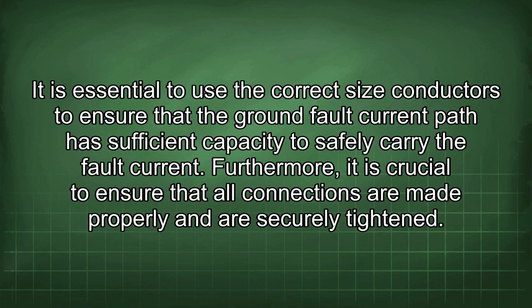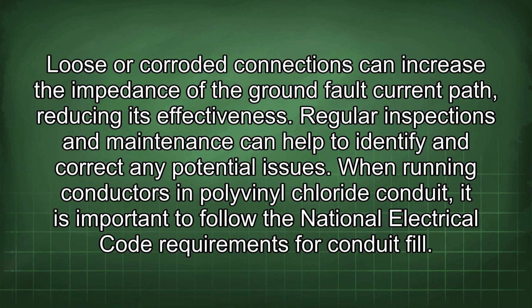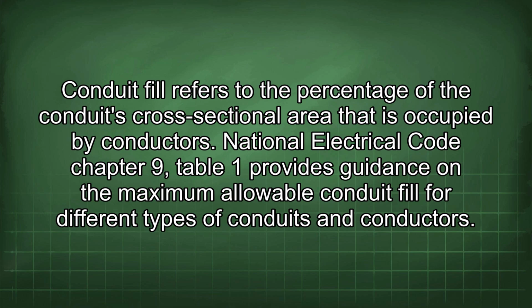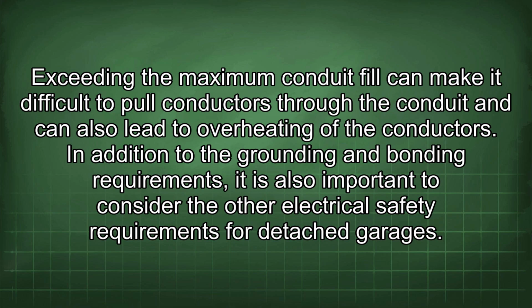Furthermore, it is crucial to ensure that all connections are made properly and are securely tightened. Loose or corroded connections can increase the impedance of the ground fault current path, reducing its effectiveness. Regular inspections and maintenance can help to identify and correct any potential issues. When running conductors in polyvinyl chloride conduit, it is important to follow the National Electrical Code requirements for conduit fill. Conduit fill refers to the percentage of the conduit's cross-sectional area that is occupied by conductors. National Electrical Code Chapter 9, Table 1 provides guidance on the maximum allowable conduit fill for different types of conduits and conductors. Exceeding the maximum conduit fill can make it difficult to pull conductors through the conduit and can also lead to overheating of the conductors.